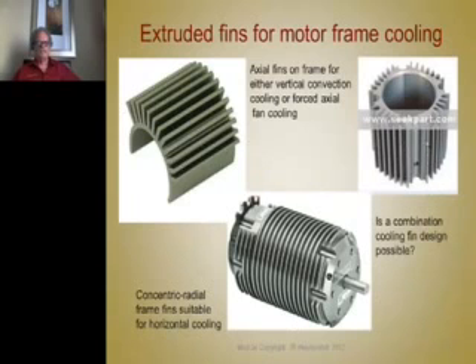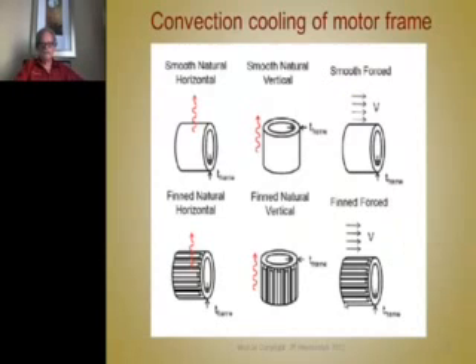You might intuitively see what it is. This would work best if the motor was mounted vertical, as would this one. But if you turned this motor horizontal, it wouldn't be very effective because you'd have some trapped air pockets. It wouldn't have very good convection velocities. Whereas if you're going to have a motor mounted horizontally, it's better to have the fins concentric like this, because you'll get natural convection flow through the temperature of the surface versus the temperature of the air going by it. But we'll show you some tests that were done on that.